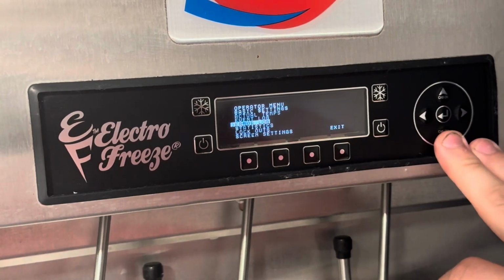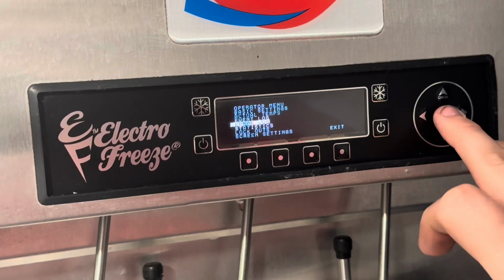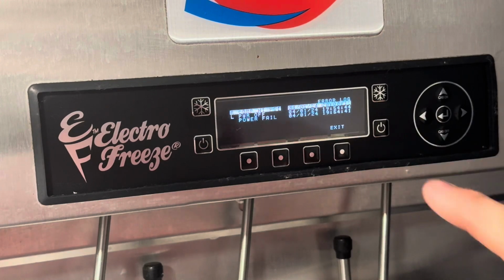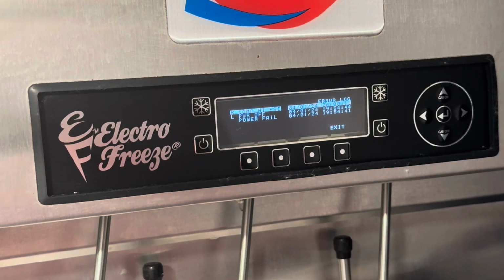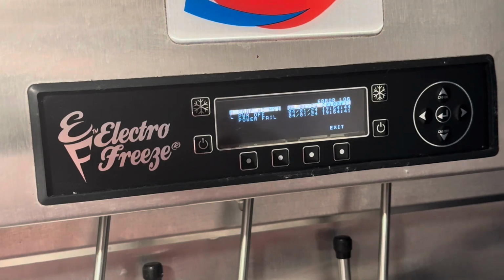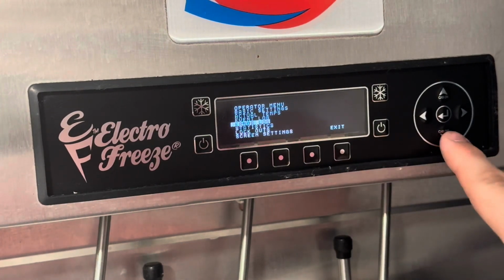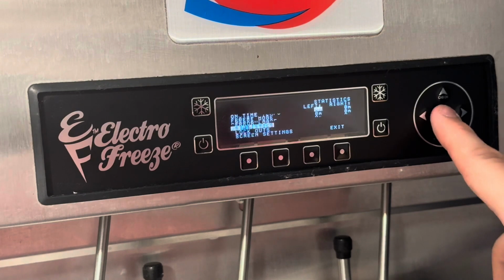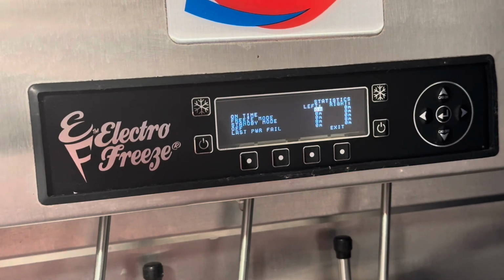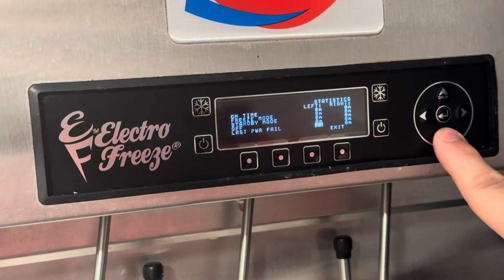Error log. This is going to show any errors that have formed in the machine. So power fail means it was unplugged, and you see compressor high PSI - that's because I currently do not have water to this machine. Statistics: this is how long your machine has been plugged in and how long the machine has run for each mode. You can scroll through these.